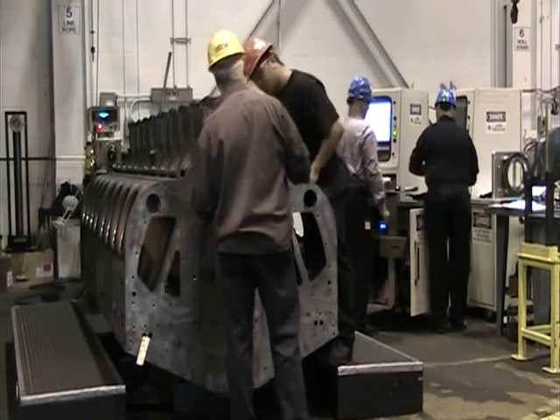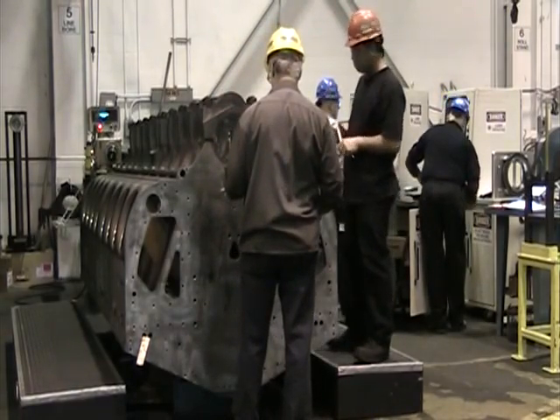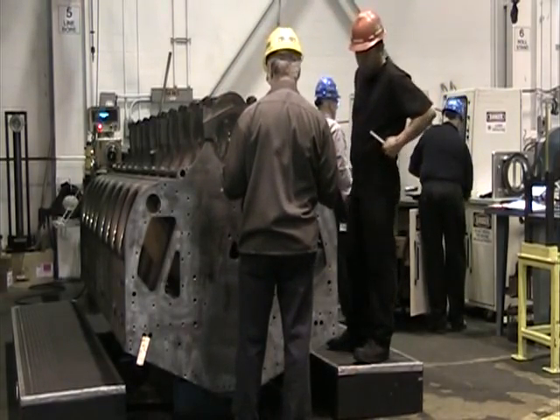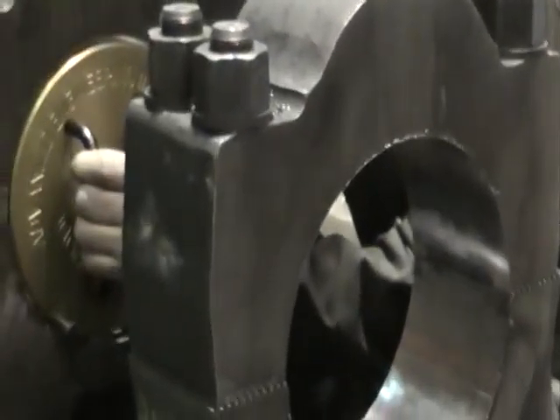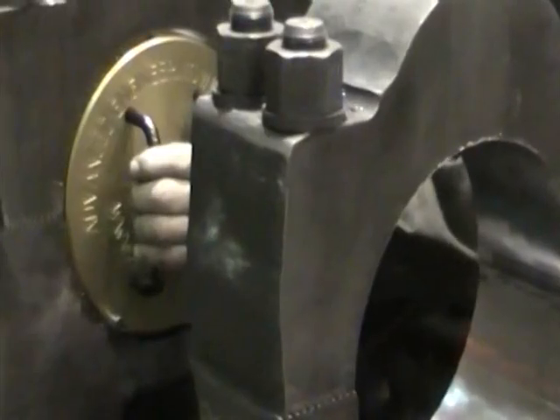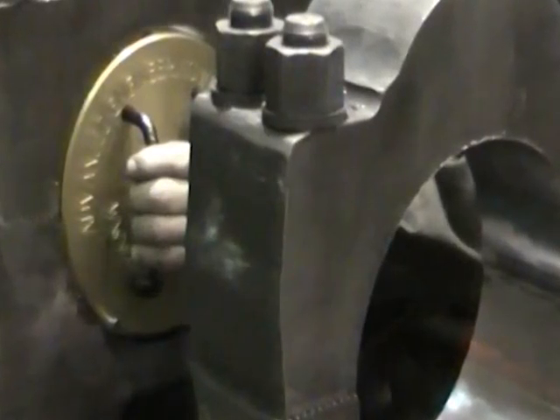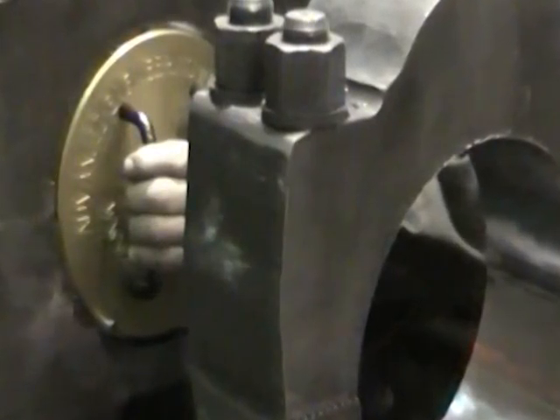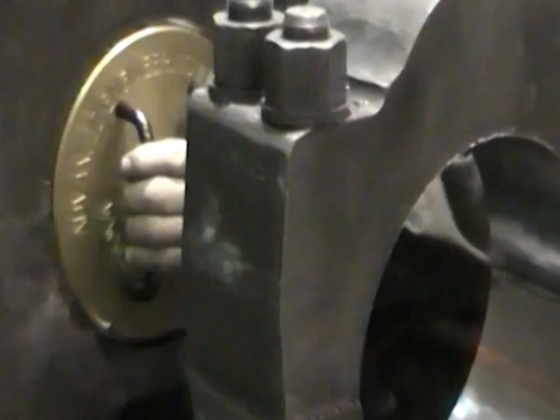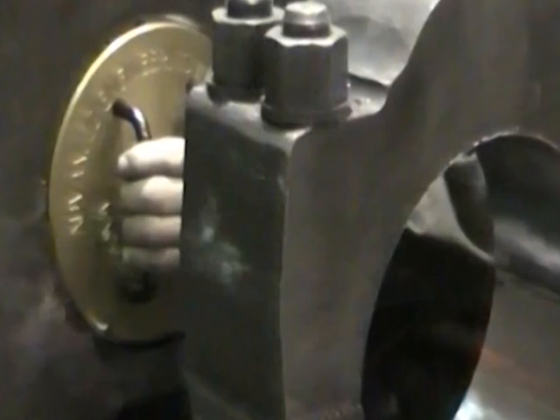Now it's time to take a reading. We read each bore twice, once in the front and once in the back. When inserting the probe into a bore, be sure to hold it directly in front of you using both hands. Twist your wrists, slightly rocking the probe back and forth to settle it into place. Failure to do so will result in faulty readings.